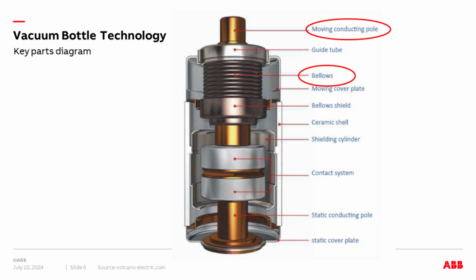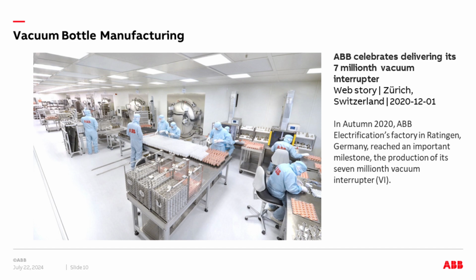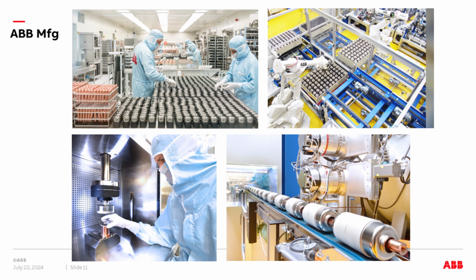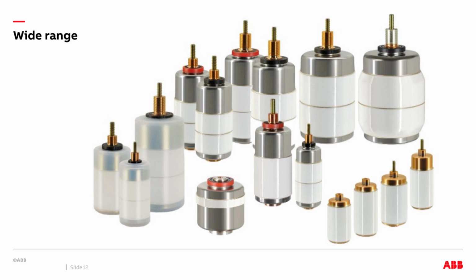Another interesting thing about the contacts and the mechanism in a vacuum bottle is the bellows. The bellows is the part that moves up and down because it's inside a vacuum and you can't risk any kind of leak. So only one of the poles moves, the other one's stationary, and the actual movement is just compressing the bellows, which allows the contacts to open. And vacuum bottle manufacturing is in a clean room environment. These are examples from the ABB factory. There's a mix of manual and automated equipment, and there are vacuum chambers, and there are quite a wide range of sizes and shapes now to handle all kinds of different levels of power.